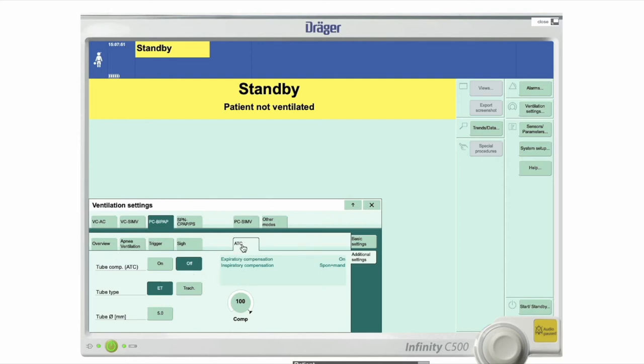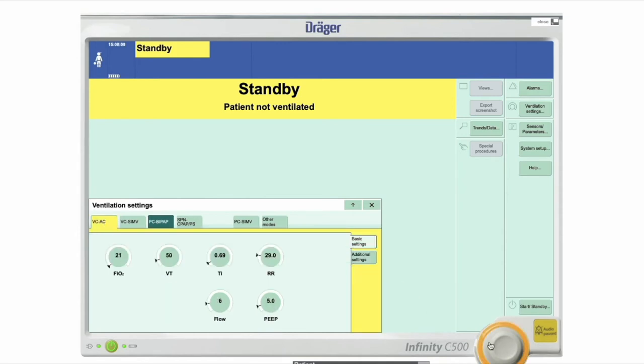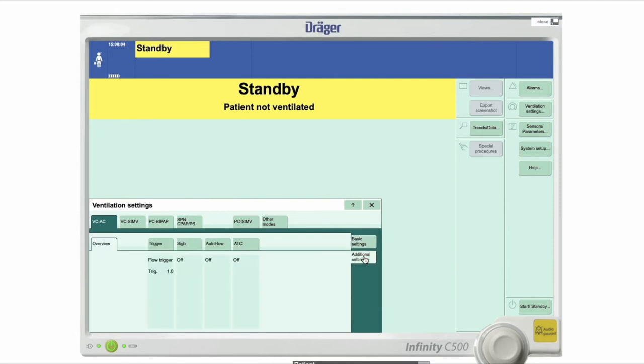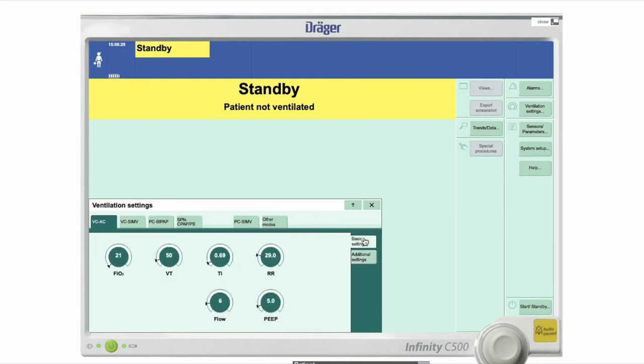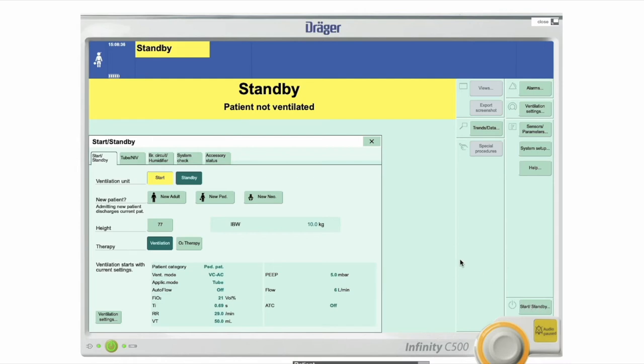Now, what you get here can differ depending on the type of ventilation you're looking at. If you put the patient in a volume mode, what you'll find is that some of it changes. So what you have here now is a thing called auto flow. And that's also very important, but it will only ever appear in a volume mode. So we use this a lot. I will tell you about it later, but you do need to know additional settings. They're in here, but they do change according to what style of ventilation you're giving. Right, so I shall now return to the start standby screen because there are some other buttons we haven't examined yet.